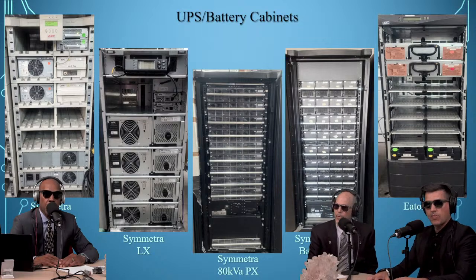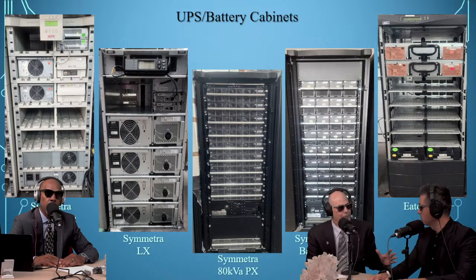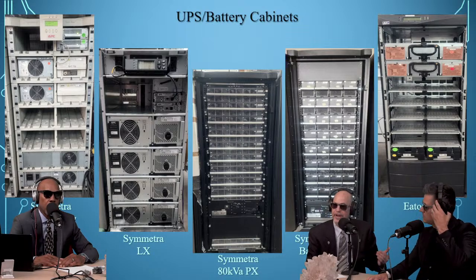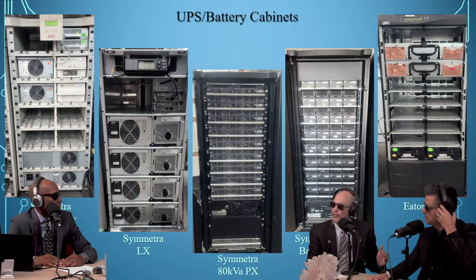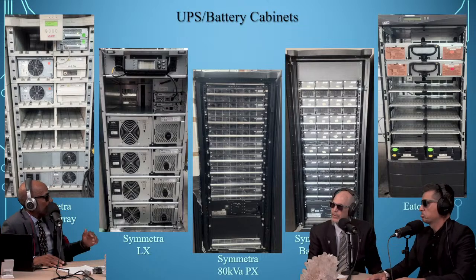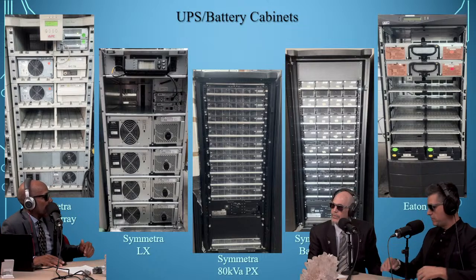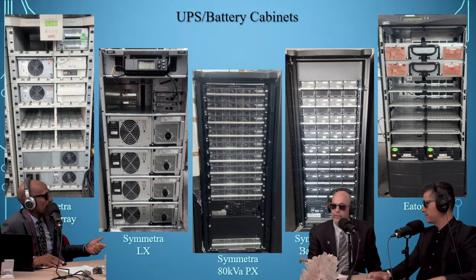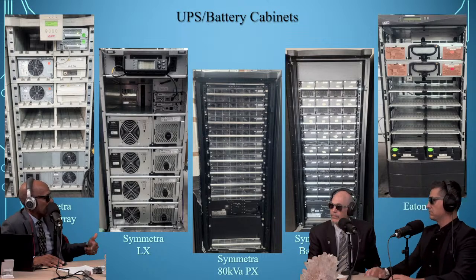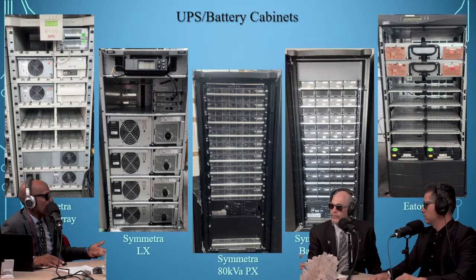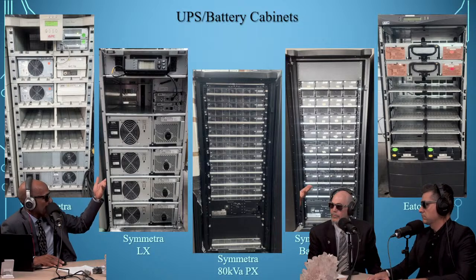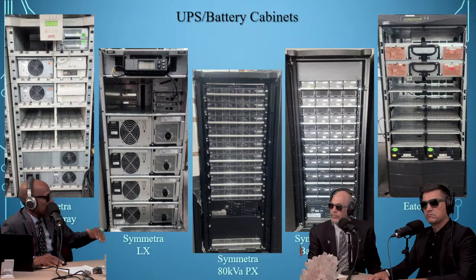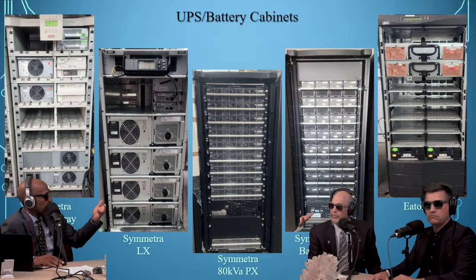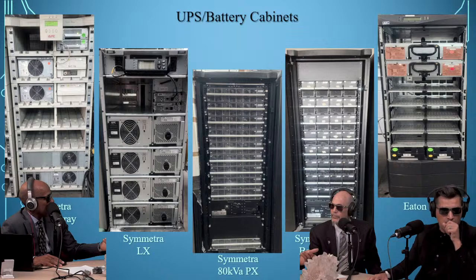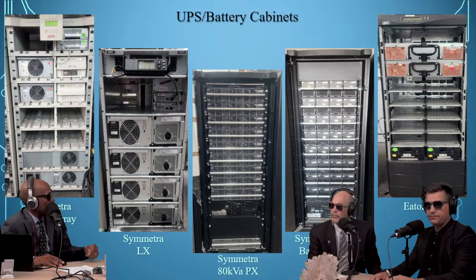Is that where, if I read it correctly or got trained on it, you only really need up to 80%? No, no - you're talking tolerance now. The furthest you should push your UPS is really 75%. You really don't want to run your UPS over 75% load, because if something happens and you're not equipped for it, it'll go out of tolerance and overload. You always want to leave a gap so that if something happens, it can absorb it, and then you get the repair done and the power module replaced.